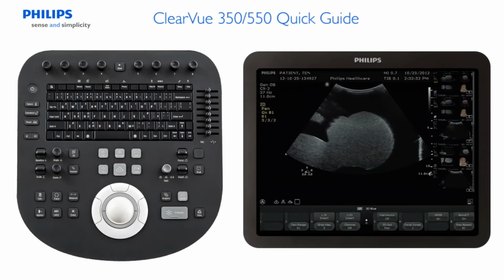Freehand 3D uses a 2D transducer to acquire volume data by physically moving the transducer over the region of interest during the acquisition. Please note that freehand 3D acquisitions are uncalibrated and therefore cannot be measured or analyzed. The following section will demonstrate the freehand 3D acquisition workflow steps using an obstetrical phantom.